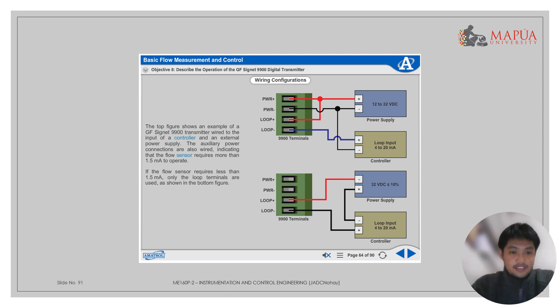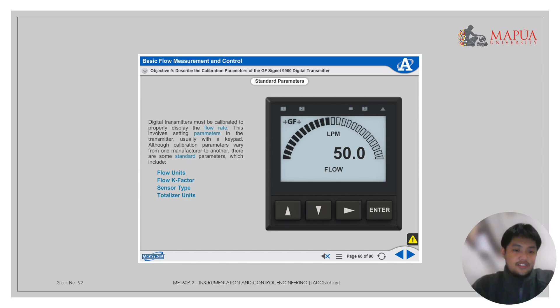The standard parameters. Digital transmitters must be calibrated to properly display the flow rate. This involves setting parameters in the transmitter, usually with a keypad, although calibration parameters vary from one manufacturer to another. There are some standard parameters, which include flow units, flow K factor, sensor type, and totalizer units.